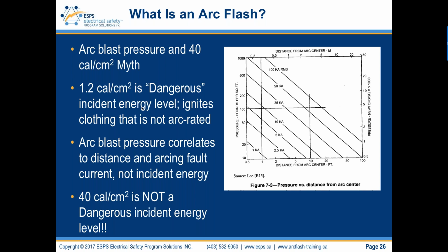That is the graph from Dr. Ralph Lee and his research back in the late 1980s. And you'll see distance on the x-axis. On the y-axis is arcing fault current and a theoretical pressure released from an arc flash in pounds per square foot.